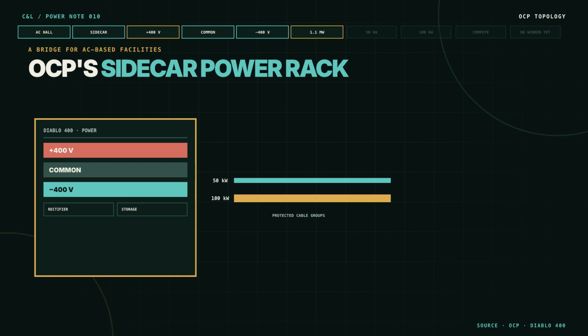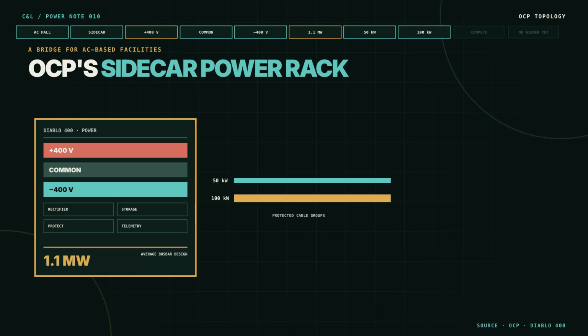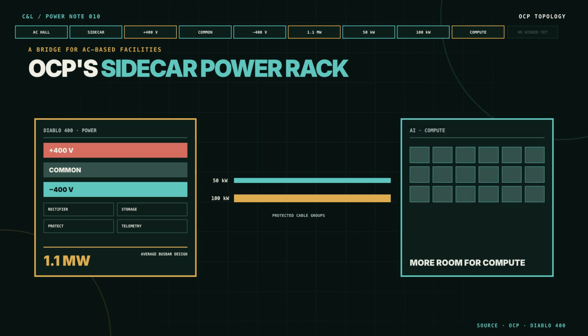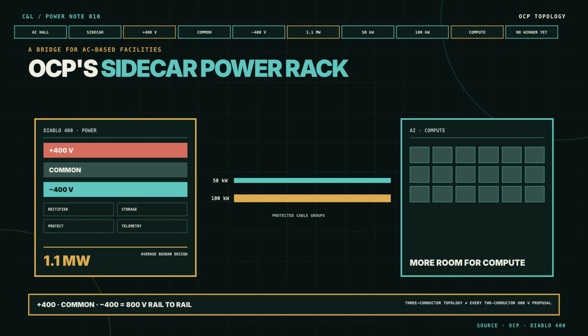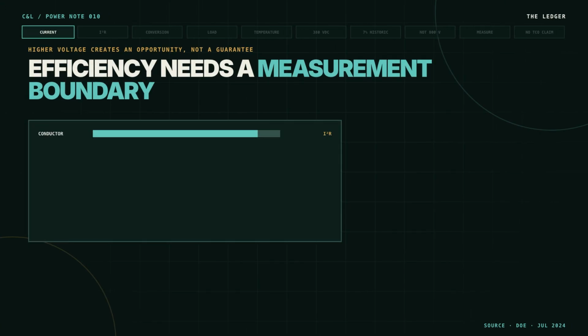The May 2025 Diablo specification describes a concealed busbar designed for up to 1.1 megawatts of average load, with protected outputs in 50 or 100 kilowatt cable groups. The sidecar can hold rectifiers, optional storage, protection, control, and telemetry, while the adjacent rack keeps room for compute. This proves active standardization work, not that one topology has won or that sidecars are final. Higher voltage creates an efficiency opportunity, not an automatic result.